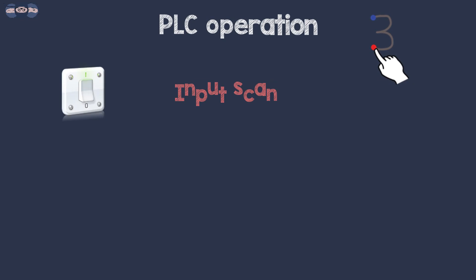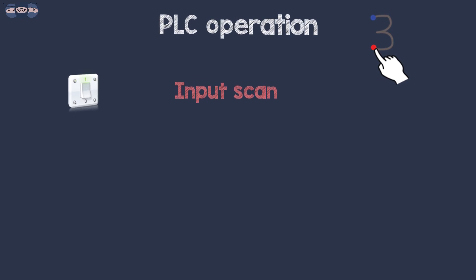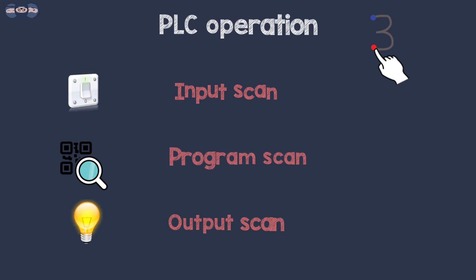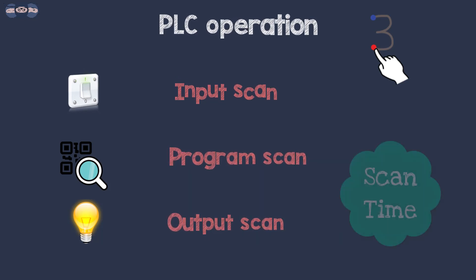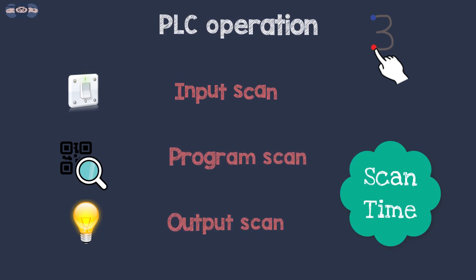A PLC operation consists of three steps: input scan — it checks the status at the input side; program scan — the CPU starts executing the application program written in PLC programming language; and output scan — it writes the data into the output module so that all the outputs are updated.